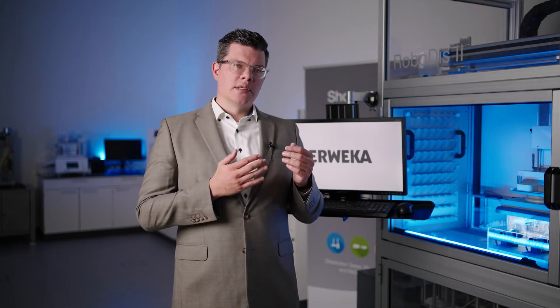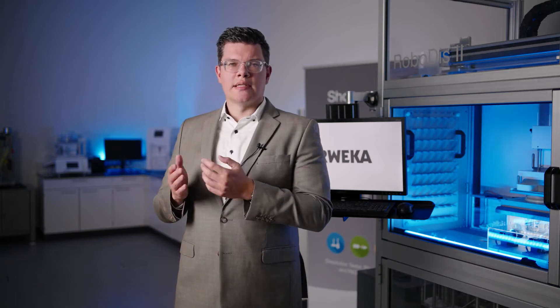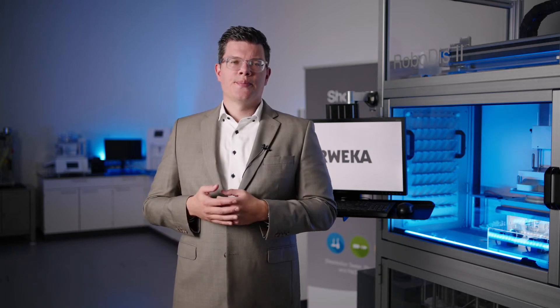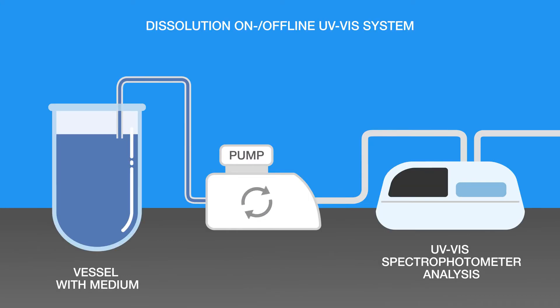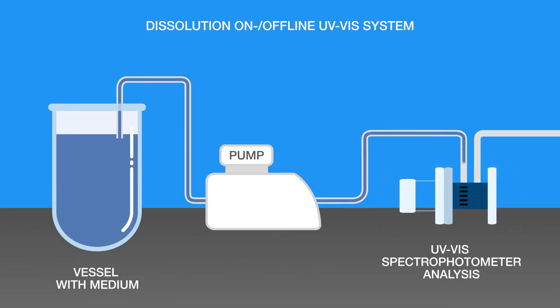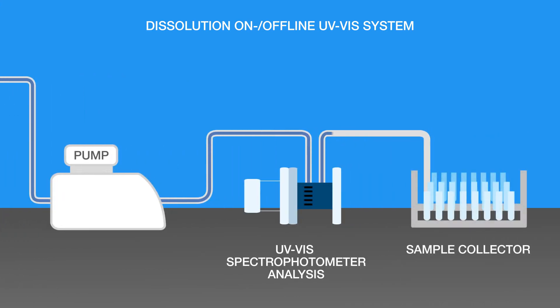The third category is an on-offline system which combines both systems. Some portion of the sample is stored, while another portion is directly analyzed. Depending on the type of on-offline system, the sequence can be different. In an on-offline UV-Vis system, the sample is first analyzed in a spectrophotometer and then afterwards stored in a vial using a sample collector.